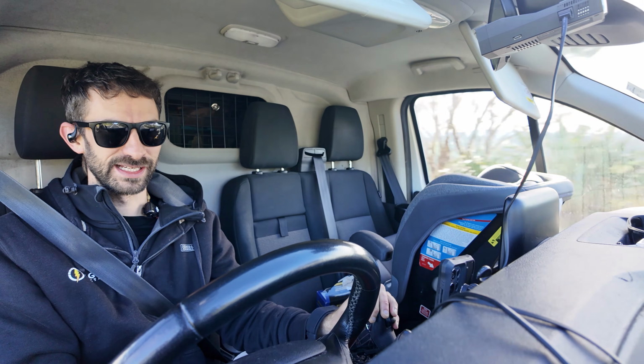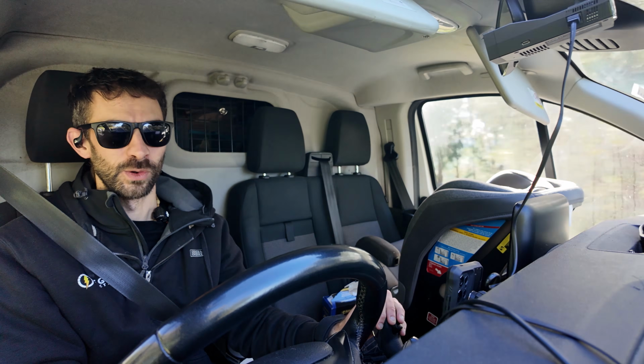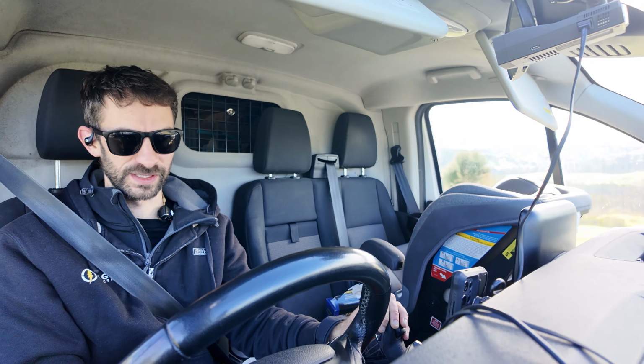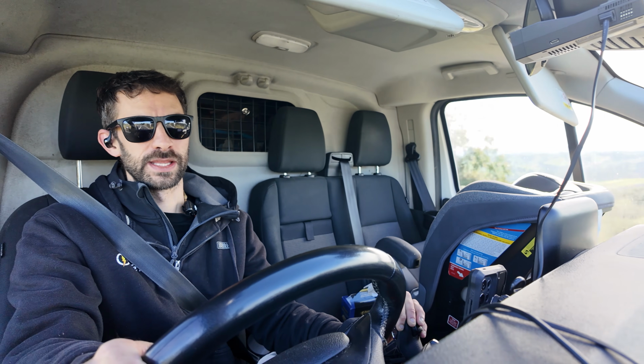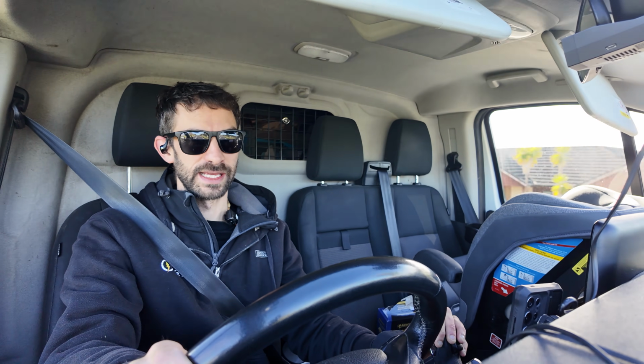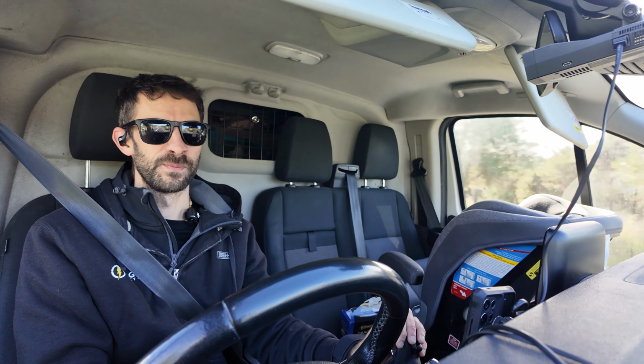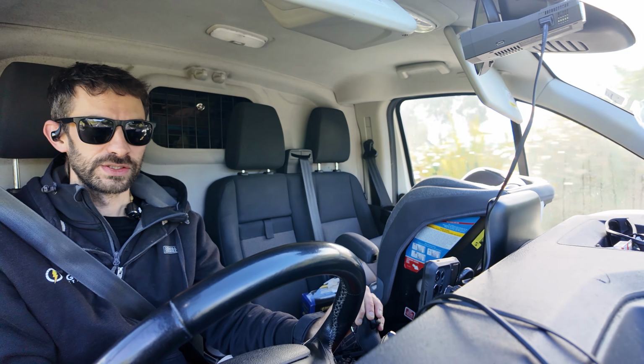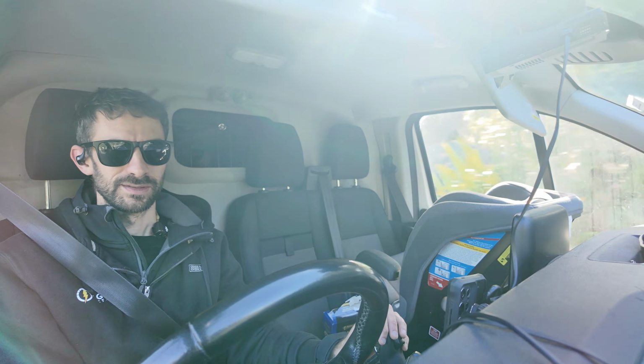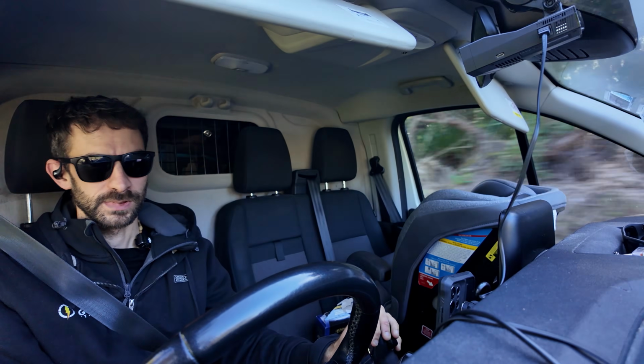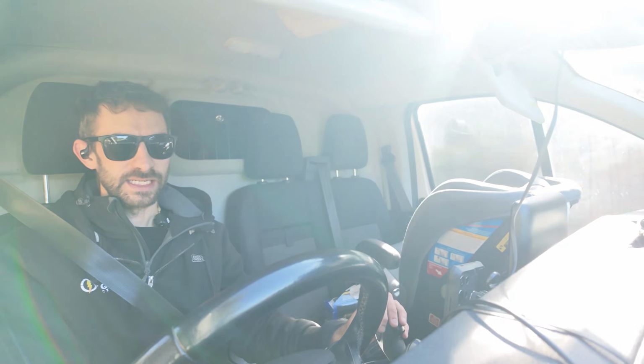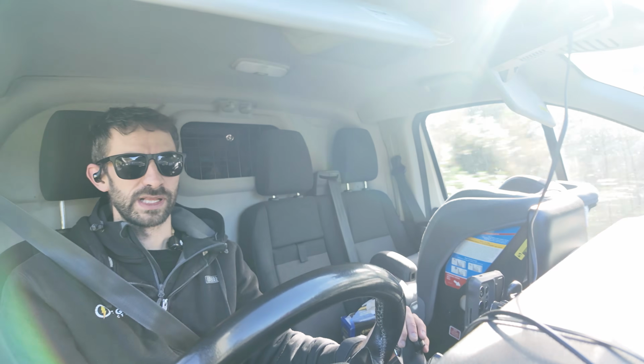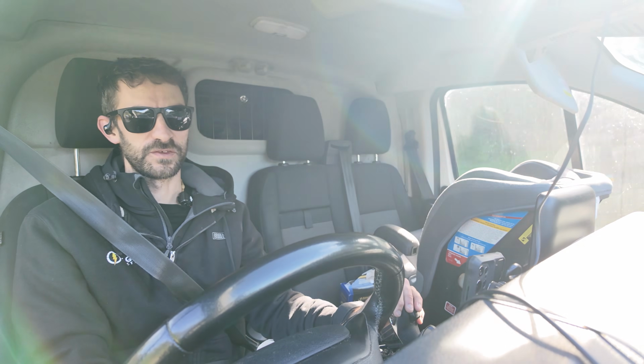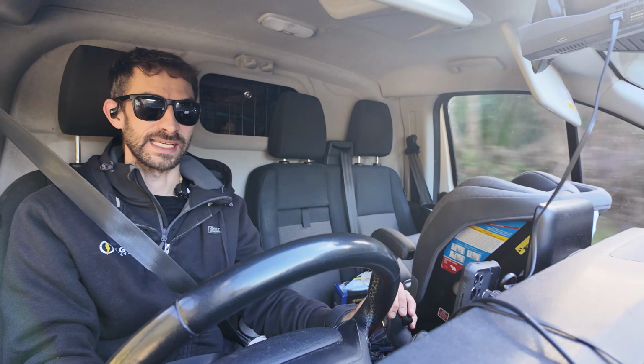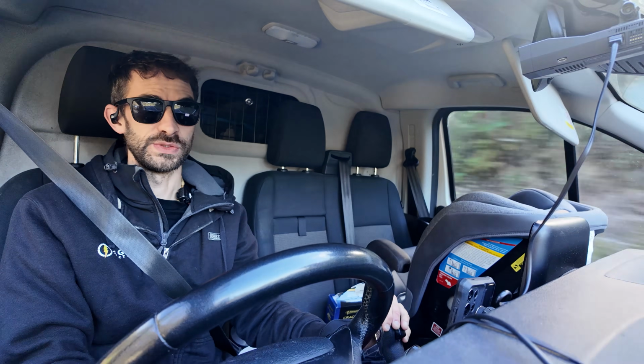So I always wondered, well, if isolated is safer, why is it not always safer? One reason is the risk of two different appliances with faults, two different conductors, creating a fault path. Another is the transient voltages that you could get if you don't earth the device. The earth electrode doesn't actually need to have a very good connection to earth in order to keep the energy levels low, the potential buildup. But the need to earth the transformer doesn't explain any benefit that might come from the earth electrode at the installation. Sure, if the transformer earth fails, then those earth rods at the houses actually become pretty important, because you actually need that protection.